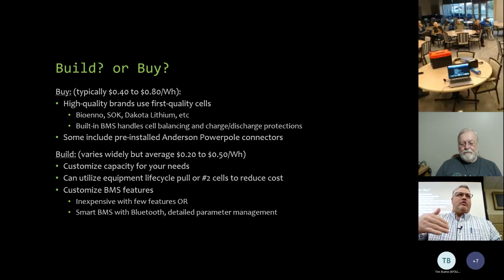They'll usually rate it so you can do 2C for 10 minutes or that sort of thing, but it's all related to that — 2C would be 12 amps for the rated period of time. You'll also see reference to the charge parameters in terms of C. A conservative charge parameter for most batteries is about 0.25C. You can do less than that, that's not an issue, it just takes longer to get there, but exceeding that can shorten the life of the battery. So in this case it would be 0.25 times 6, and that's our charge rate there.